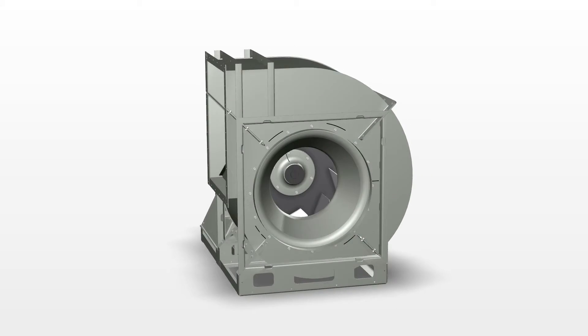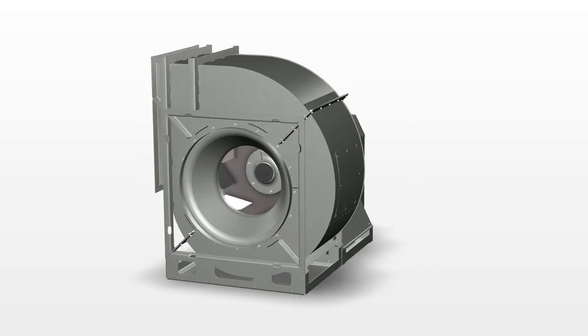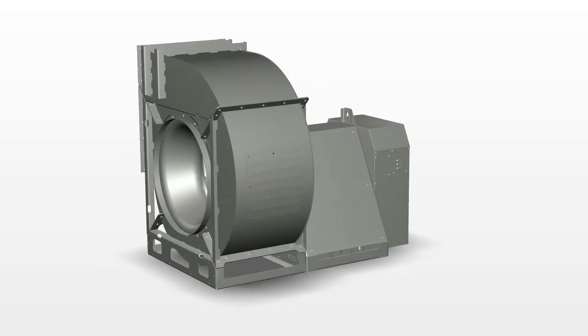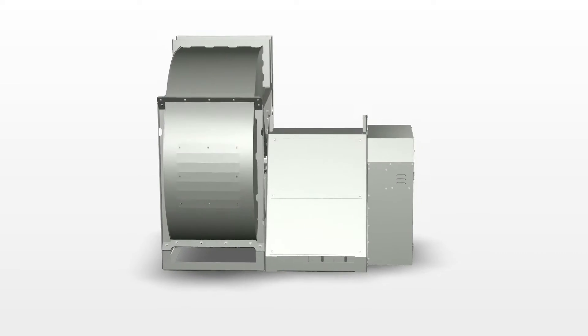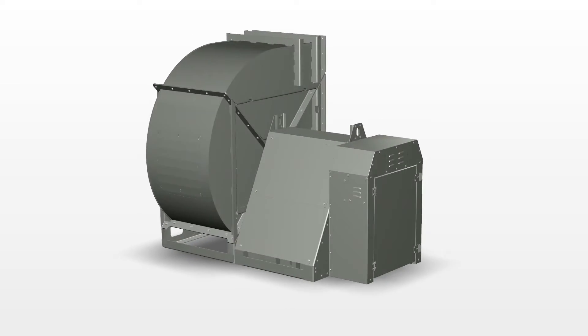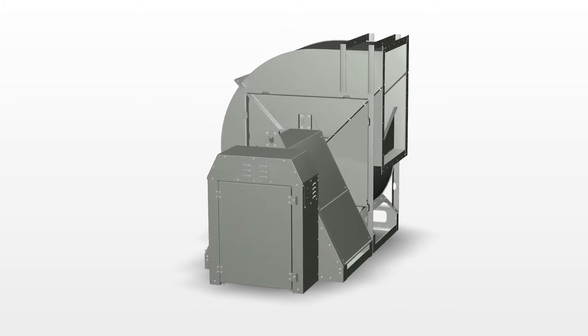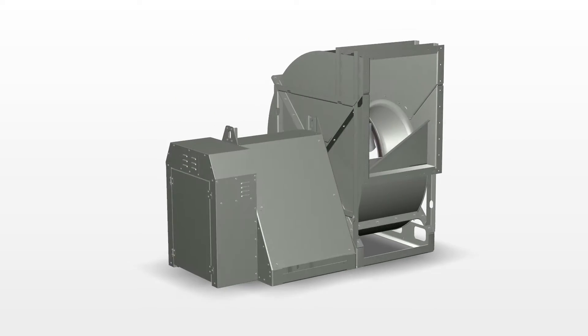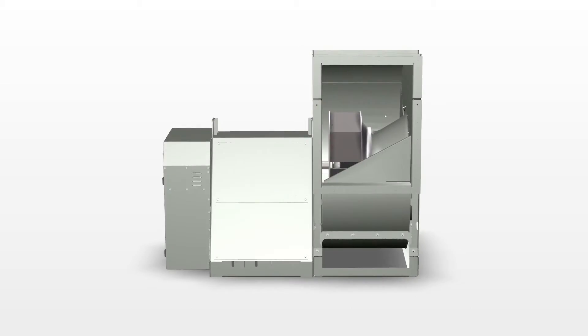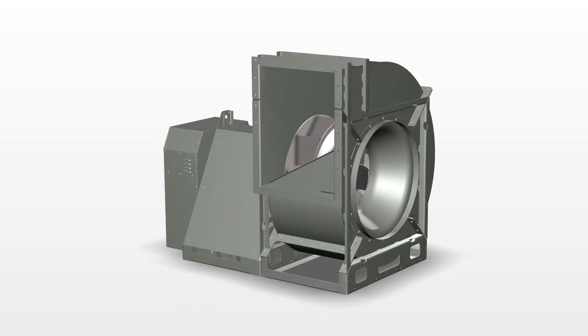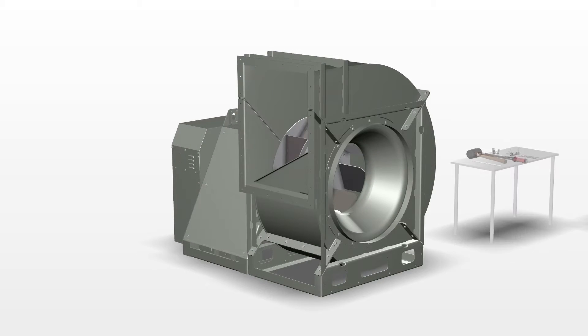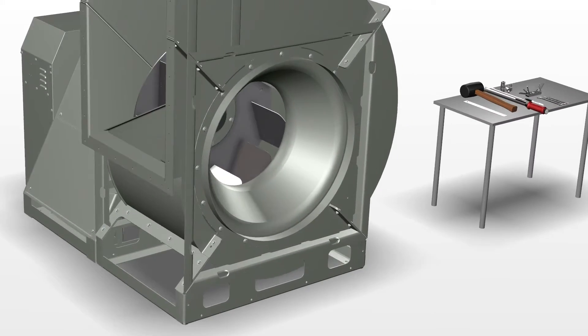In this presentation we will be illustrating how to take apart and reassemble a quad split fan. This style of fan comes fully assembled from the factory. The tools that you may need are a rubber mallet, allen wrenches, a torque wrench with the proper size socket for your hub, the wrenches to fit your cone bolts, split bolts, and base bolts.